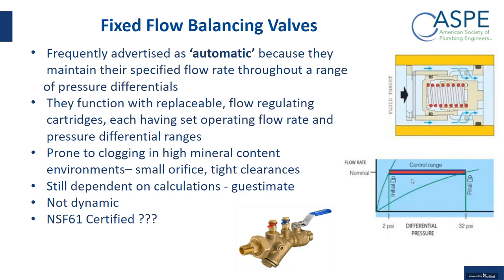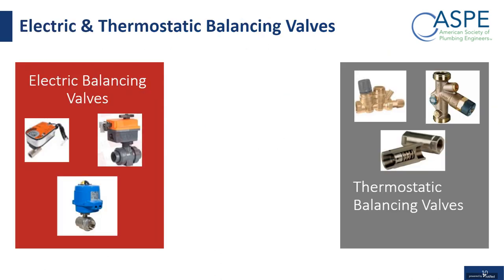And then historically, a lot of these valves have come from the hydronics industry, and because they're in hydronics and not in potable water systems like domestic hot water systems, a number of these valves over the years have not been NSF 61 certified. I have seen recently at least one manufacturer offering this valve with NSF 61 certification. So I would just caution you, if you're using these valves and you want to stay compliant, make sure that they are NSF 61 certified. They should be stamped on the valve with the agency that certified them. So again, if you want to be compliant and you're using these valves, just make sure that they are NSF 61 certified.